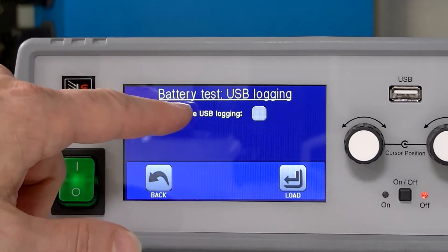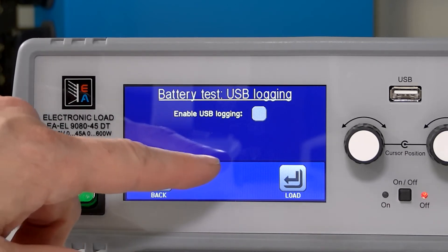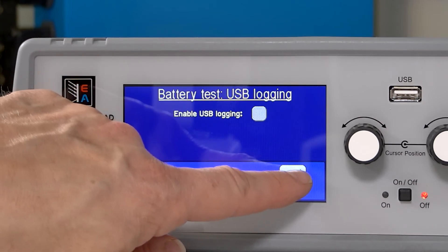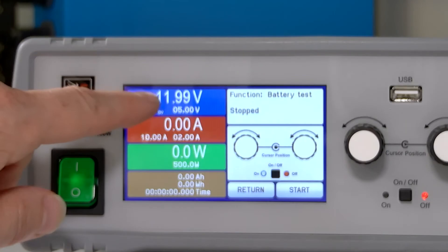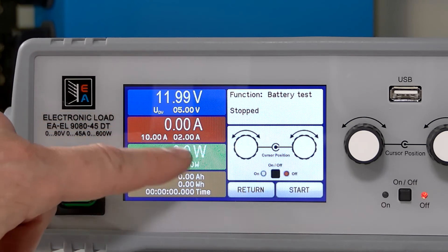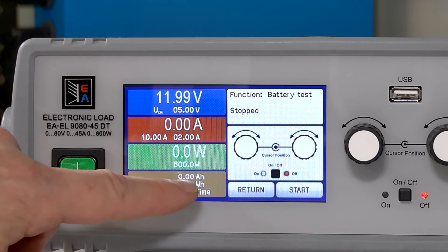Here you can select whether you want the battery test data to be logged onto USB, which is right over here — you can plug in a thumb drive and download data directly onto that drive. If I hit load, now our load is ready to start. The current will be going between 10 and 2 amps, our power limit will be 500 watts, and here are our discharge limits which you'll see starting to count once the test begins.